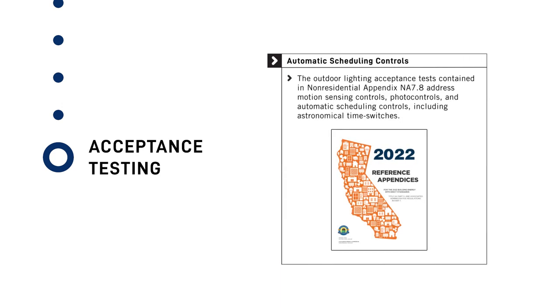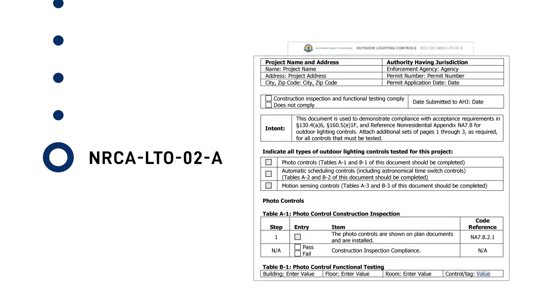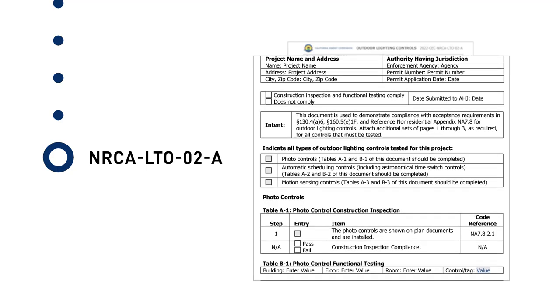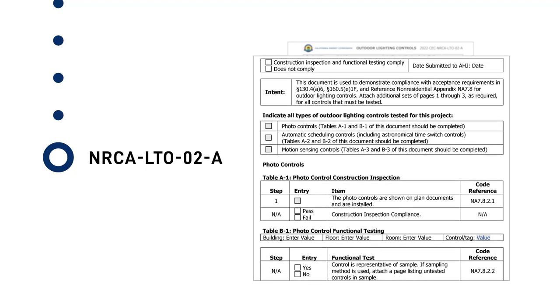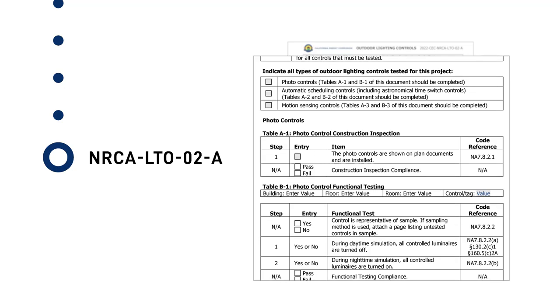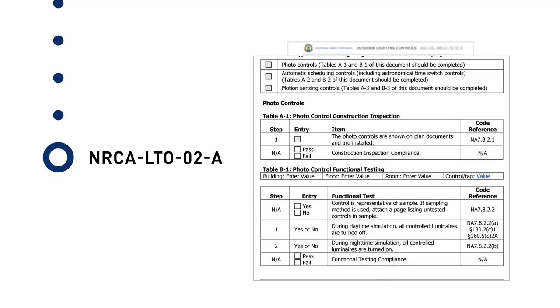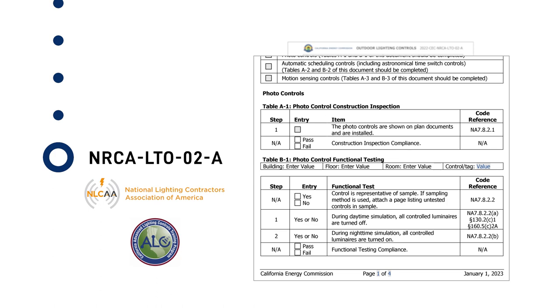The Outdoor Lighting Acceptance Test, contained in non-residential appendix NA 7.8, addresses motion sensing controls, photo controls, and automatic scheduling controls, including astronomical time switches. Acceptance test results for outdoor lighting controls are documented by the Certified Lighting Controls Acceptance Test Technician on the Certificate of Acceptance NRCA-LTO-02-A. The official Lighting Controls Certificates of Acceptance may only be accessed and submitted by a Certified Lighting Controls ATT through their Approved Acceptance Test Technician Certification Provider, or ATTCP, portal. It is important to remember that an official Lighting Controls Certificate of Acceptance will contain the ATTCP's logo to differentiate it from the information-only version of the form.